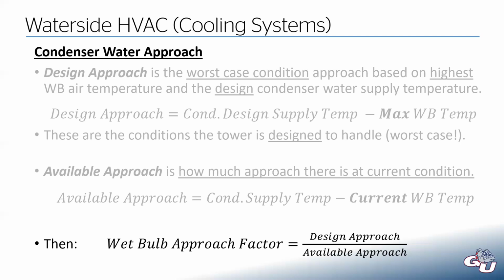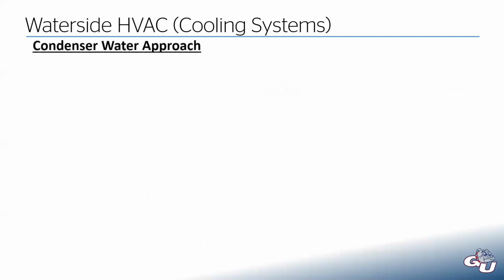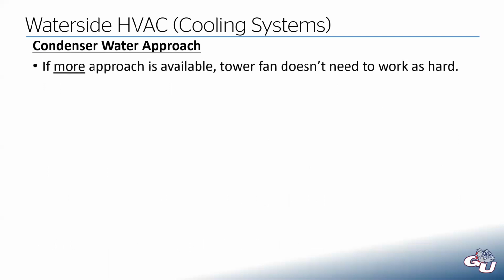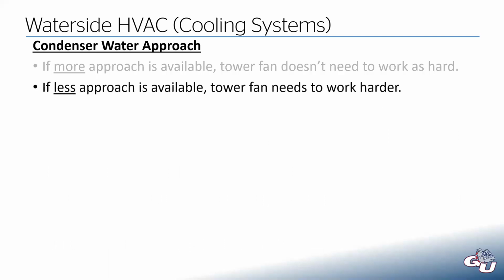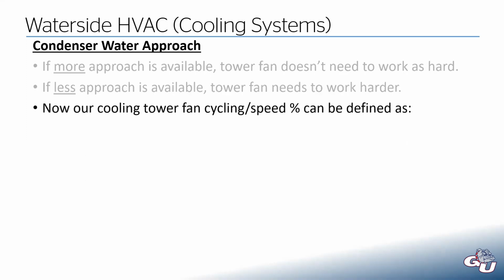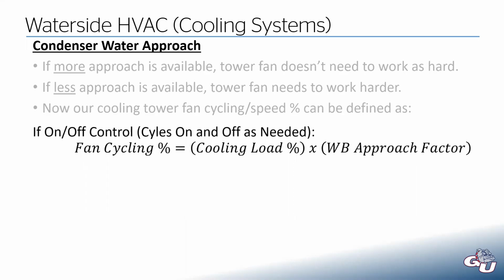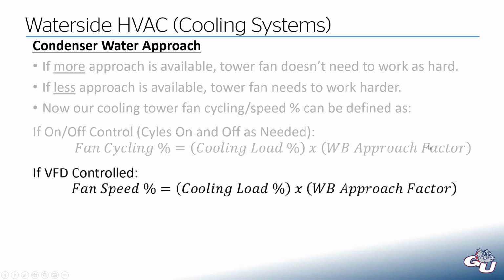Conceptually, your heads might be spinning a little bit, but bear with me. I'll have an example here in a sec that helps illustrate this. If we have more approach available, meaning we have a lower wet bulb temperature, that means our tower fan doesn't need to work as hard. Conversely, if we have less approach available, our fan needs to work harder. So now our cooling tower fan, either cycling or our speed percent, could be defined as our fan cycling percent, if we have a cycling fan, would be our cooling load percent, because we know that our fan cycling will be proportional to our cooling load, multiplied by this wet bulb approach factor. If we have a VFD controlled fan, it's the same equation. It's just instead of how much it's cycling on, this is the fan speed at which it's going to run.